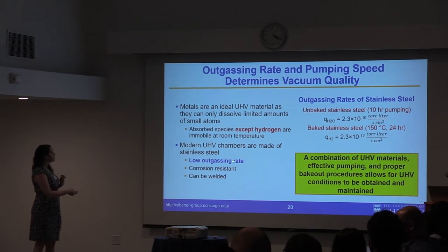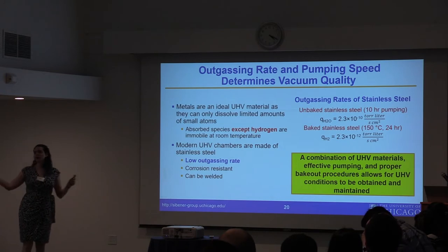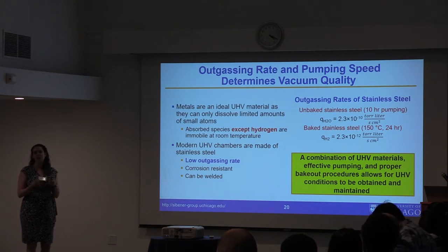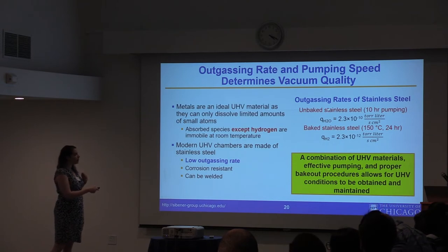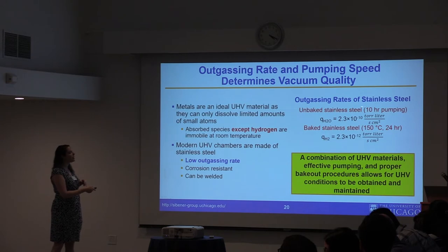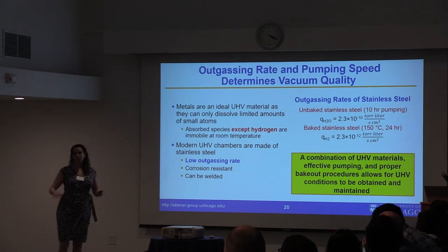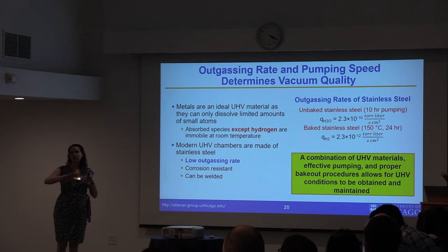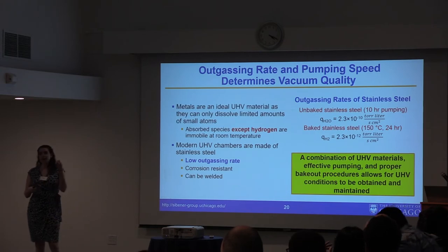Most UHV chambers today are made of stainless steel because it has a lower inherent outgassing rate, is corrosion resistant, and can be welded. As-manufactured stainless steel has water desorbing at about 2×10⁻⁹ torr·liters per second per unit area. That will result in a higher chamber pressure. But if you bake your stainless steel — raising it above at least 100°C to drive off water from the interior and facilitate desorption of trapped gases — you can get the outgassing rate down to 10⁻¹² torr·liters per second, allowing for a much cleaner system.